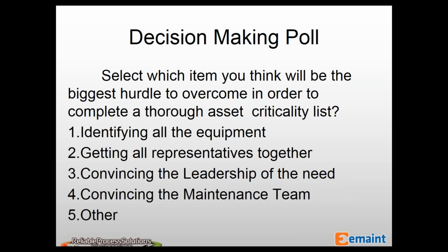then the criticality in that particular area may change. So in this particular case, you'd have an overall ranking for your system, and then you may have a much higher criticality ranking for a particular component, and you may want to divide that up, give it its own equipment number for an individual ranking, or you may assign it to the operating asset that it is intended to service. So there's, again, a couple of different ways you can approach that, but there's nothing wrong with taking the overall system as a piece of equipment, but be considerate of specific cases, and don't forget your operating context. HVAC, air conditioning may be more important in Texas or New Mexico than it is in Ottawa.